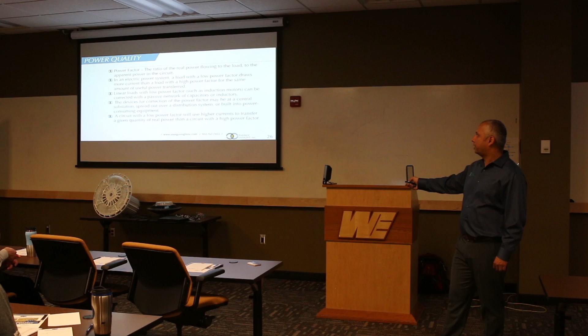Harmonics - this is another one that has picked up a lot in the last few years. It's a result of non-linear electric loads causing power quality problems, resulting in increased heating in equipment and conductors, misfiring in variable frequency drives, and a ton of other problems. So power factor and harmonics are the two things you have to work on.